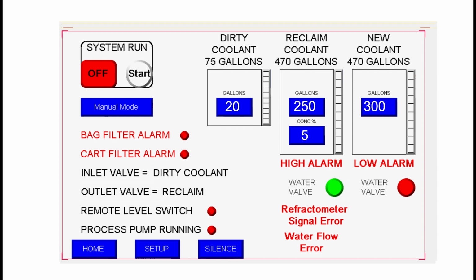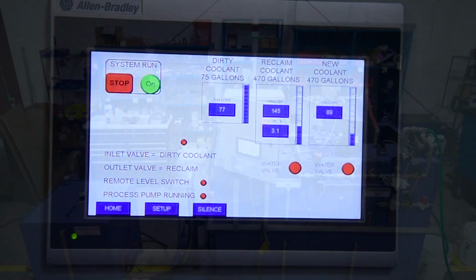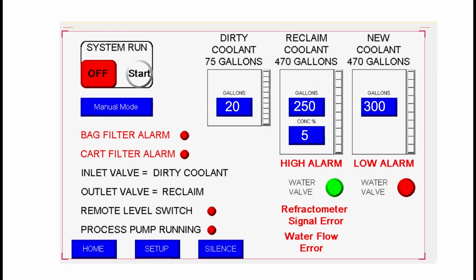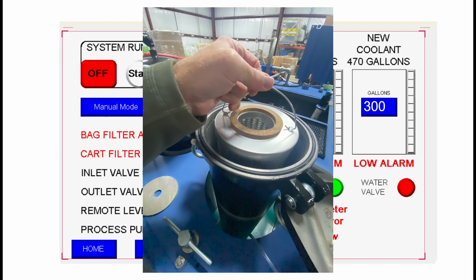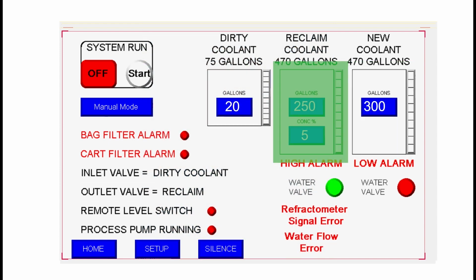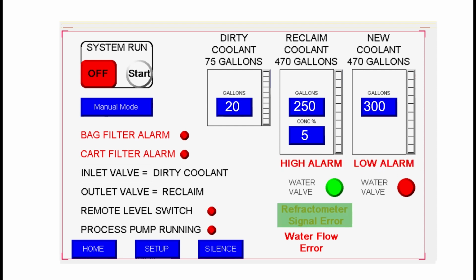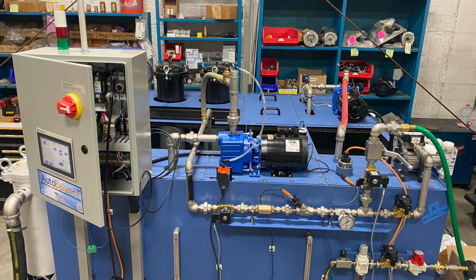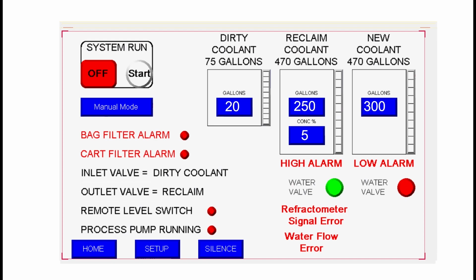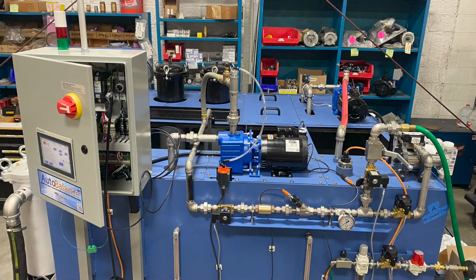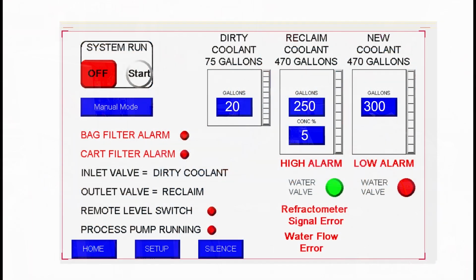The auto balance controller also indicates any alarm and maintenance functions via both an audible buzzer and visual stack light. Alarms and maintenance indications include bag filter plugged indication, which means the bag filter must be replaced. Cartridge filter plugged indication, which means cartridge filters must be replaced. Tank A, B, high, and low alarms. Refractometer signal error, which means a signal has been lost from the refractometer, either due to malfunction or loose wire requiring rectification. Water flow error, meaning no coolant concentrate rebalance water has been sensed by the flow totalizer, which means either a malfunction or loose wire requiring rectification.